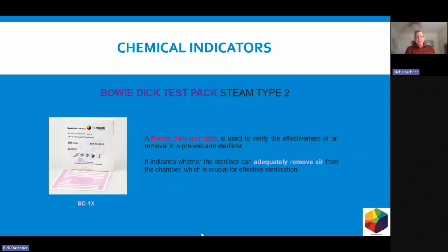The Bowie-Dick test, again, it's considered a type 2, and it depends on what the requirement is of the facility or manufacturing facility company that runs this test. So it's used to verify the effectiveness of air removal in a pre-vacuum sterilizer. Again, if you haven't seen one of these before, it's a card that changes color. So you see the card there, and it's got pink. That'll change color, and that is inside the box behind it. That has stacks of cardboard to challenge the device, so the validation is proper. So they put that card within a deck of cardboard. Inside that box, you put the whole box in the sterilizer, and it will indicate whether or not the air removal was appropriate in the pre-vacuum sterilizer. It indicates whether the sterilizer can adequately remove air from the chamber, which is critical for effective sterilization.